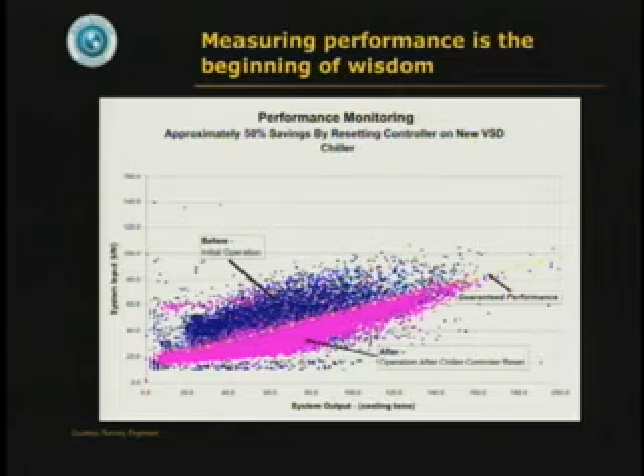Here's another case where it turned out immediately from measurement that the chillers were operating less efficiently than specified. The second and third ones were turning on early because the controls weren't set up right, and the maximum load, contrary to the owner's expectation, never got to the point where they would have needed one million dollars worth of additional chiller that they were about to buy.